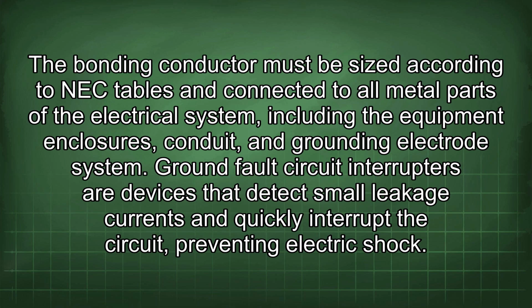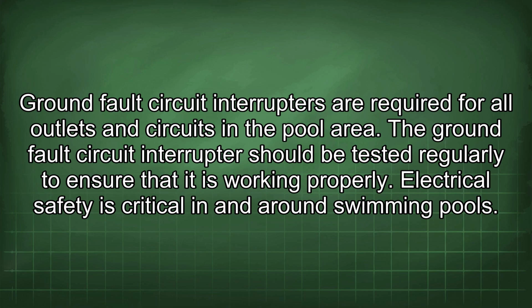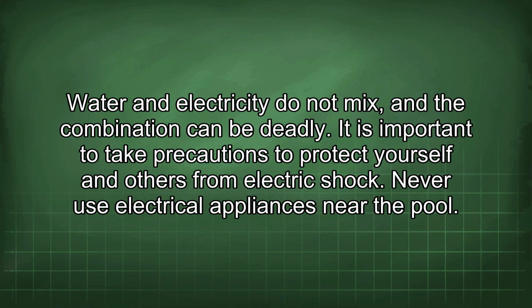Ground fault circuit interrupters are devices that detect small leakage currents and quickly interrupt the circuit, preventing electric shock. Ground fault circuit interrupters are required for all outlets and circuits in the pool area. The ground fault circuit interrupter should be tested regularly to ensure that it is working properly. Electrical safety is critical in and around swimming pools. Water and electricity do not mix, and the combination can be deadly. It is important to take precautions to protect yourself and others from electric shock.